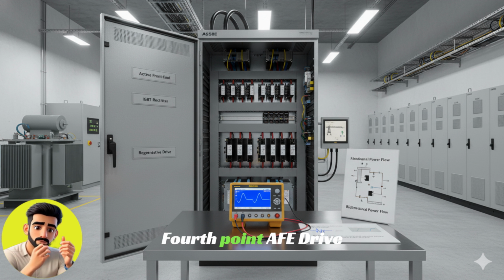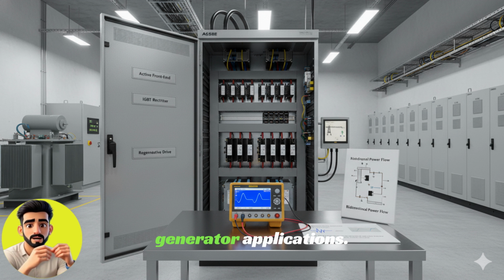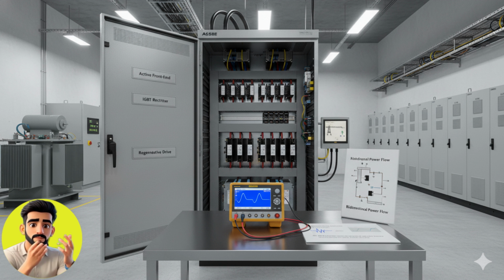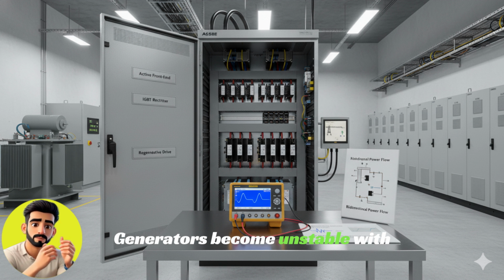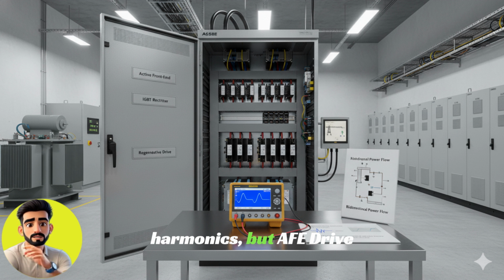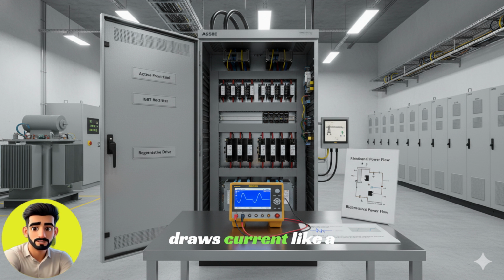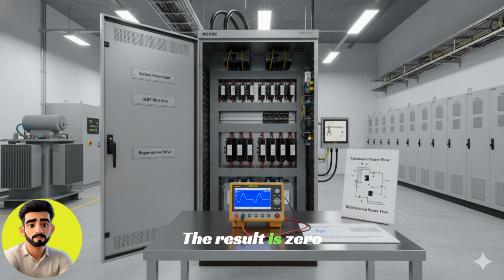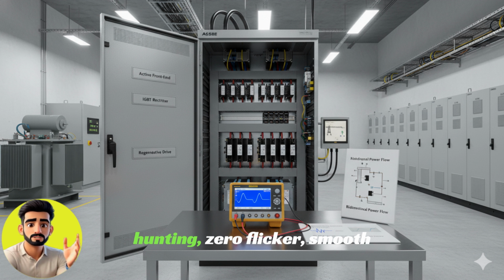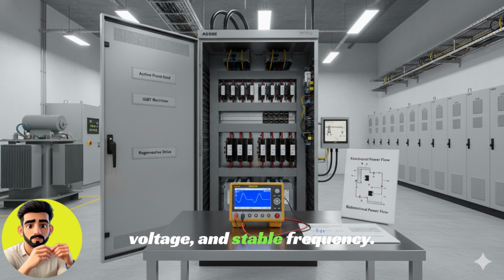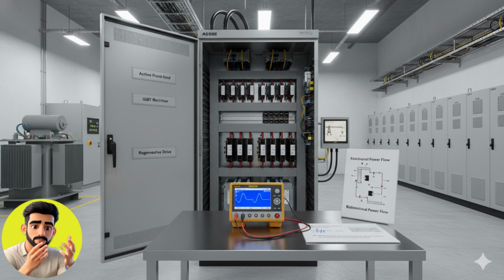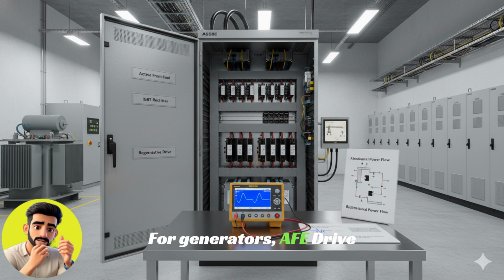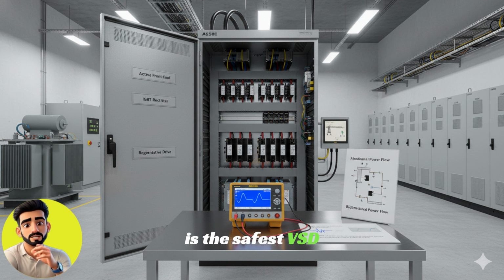Fourth point. AFE drive systems are perfect for generator applications. Generators become unstable with harmonics, but AFE drive draws current like a pure sine wave. The result is zero hunting, zero flicker, smooth voltage, and stable frequency. For generators, AFE drive is the safest VSD technology.